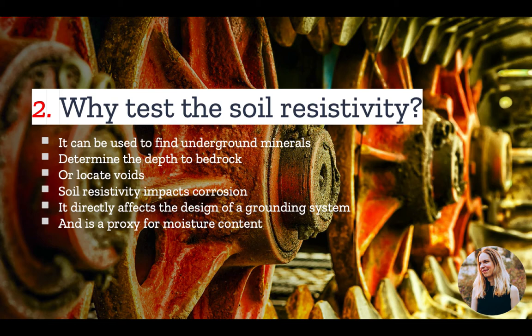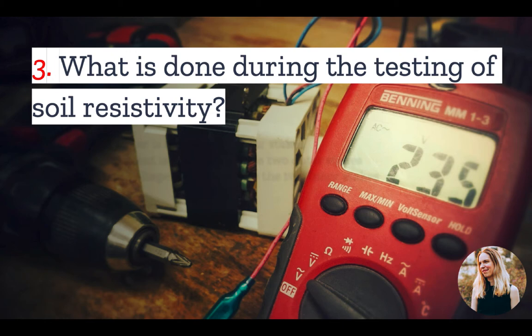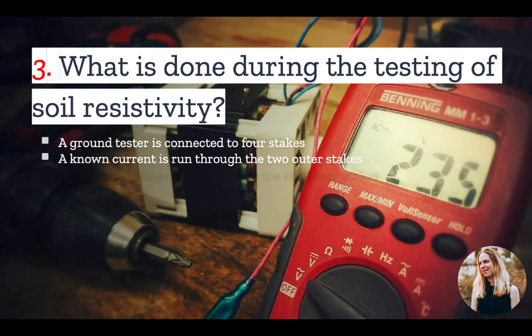Number three: what is done during the testing of soil resistivity? There are a couple different methods that are used, but at a high level, it involves connecting a ground tester to stakes that are embedded in the ground. In one version of the test, you use four stakes. The tester will run a current through the two outer stakes, and the current will run through the ground to the two inner stakes, which measure the drop in voltage.